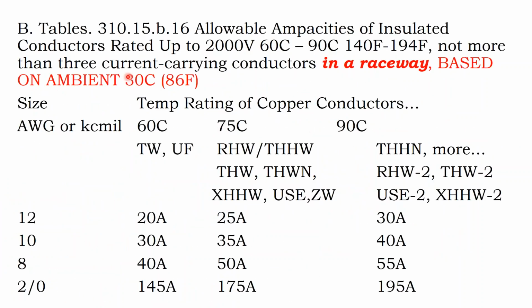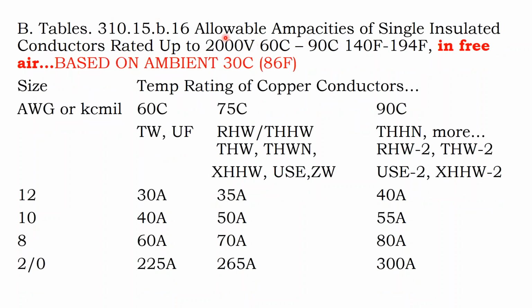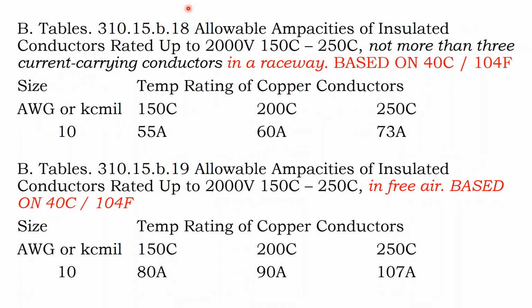But then you have to pick: do I need to read table 310.15 B16, or B16 for free air, or do I go to B18 for in a raceway, or B19 for in free air? You match up your temperature condition, you match up your environmental case, and then you read the chart to see, okay, number 10, I can have all the way up to 73 amps.